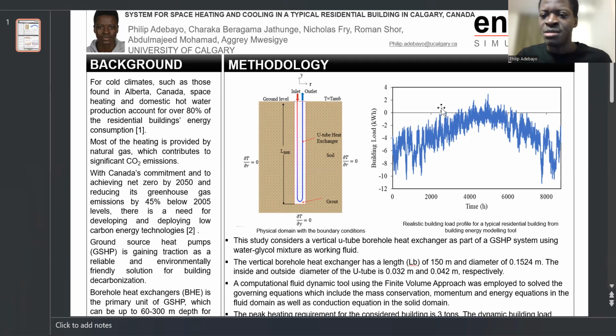Here is the building load profile generated from OpenStudio and EnergyPlus for a typical residential building in Calgary. As you can see, most of the time we are extracting heat from the ground, and the amount of time that we have the building load requirement greater than 0 is very minimal compared to the amount of time when we have the building load requirement lesser than 0.